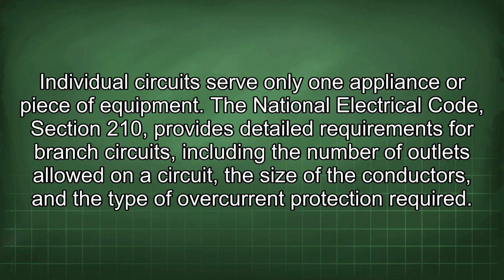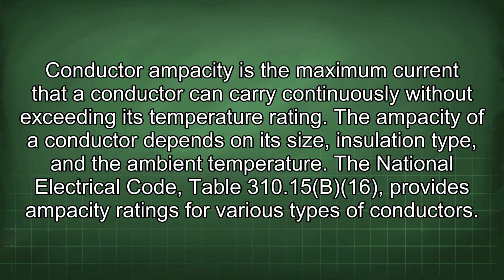The National Electrical Code, Section 210, provides detailed requirements for branch circuits, including the number of outlets allowed on a circuit, the size of the conductors, and the type of overcurrent protection required. Conductor ampacity is the maximum current that a conductor can carry continuously without exceeding its temperature rating. The ampacity of a conductor depends on its size, insulation type, and the ambient temperature. The National Electrical Code, Table 310.15(B)(16), provides ampacity ratings for various types of conductors.